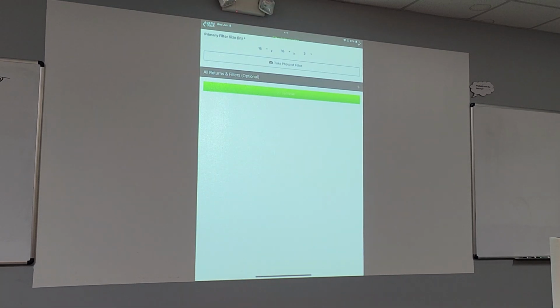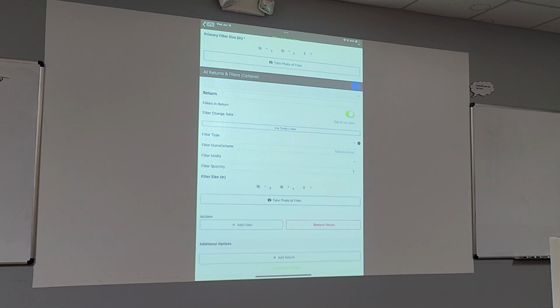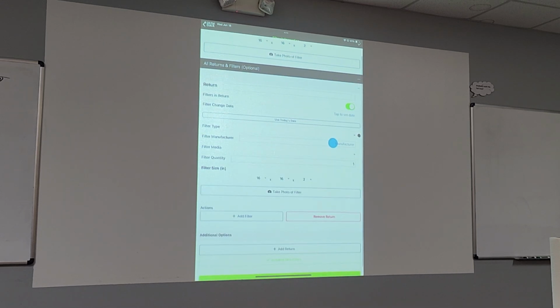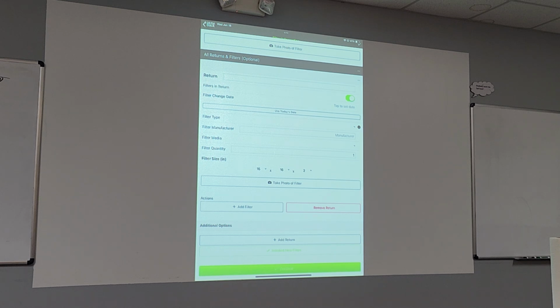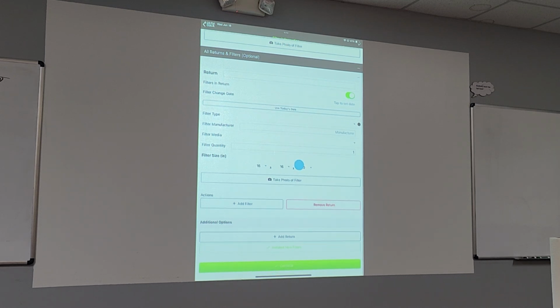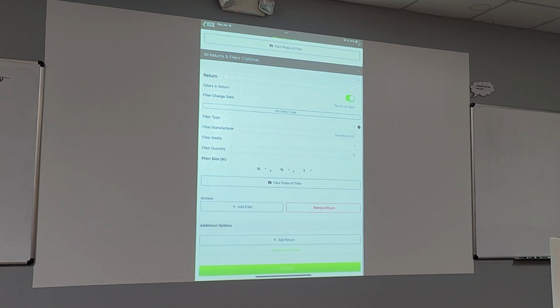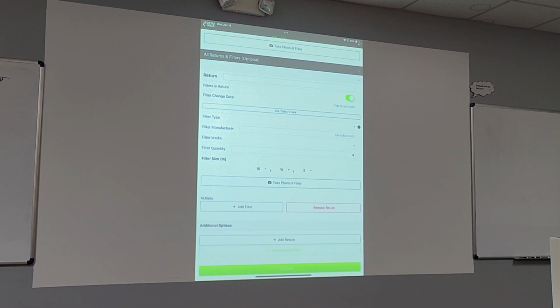But if you hit the blue button here, I can pull up a bigger filter page. This is important because one of the calculations we make is air velocity across the filters. We need to know the surface area of the filters because we can calculate the flow volume, but we need the surface area to calculate the velocity. So if I leave it as just one 16 by 16 filter, that wouldn't be accurate. It's actually got four of them in here. So if I change the filter quantity to four, that quadruples the surface area. You've got to make sure you have that information in here.